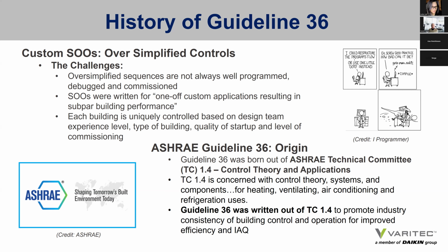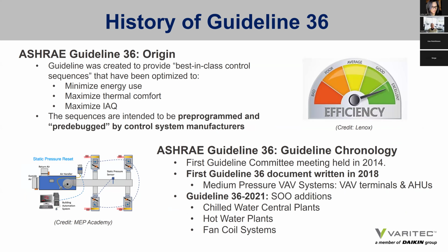Each building is uniquely controlled based on the design team's experience level, type of building, quality of startup, level of commissioning, and the capability of the service techs who actually work on that building. So Guideline 36 was born out of ASHRAE Technical Committee 1.4, which specializes in control theory and application. It was written to promote industry consistency of building control and operation for improved efficiency and indoor air quality. And I can't help but think what also drove it was ASHRAE's commitment to decarbonization and to creating healthier environments. So the guideline was created to provide best-in-class control sequences that have been optimized to minimize energy use, maximize thermal comfort, and maximize IAQ.